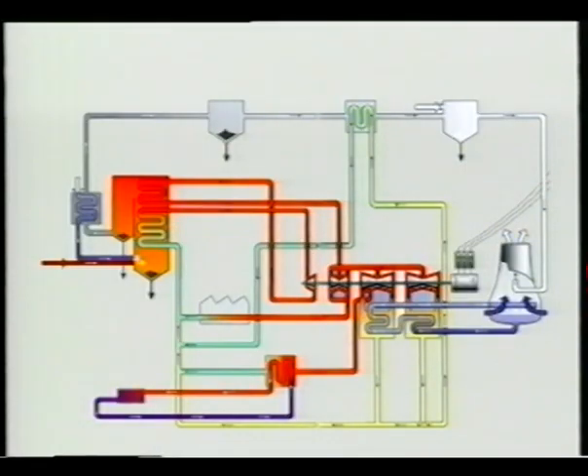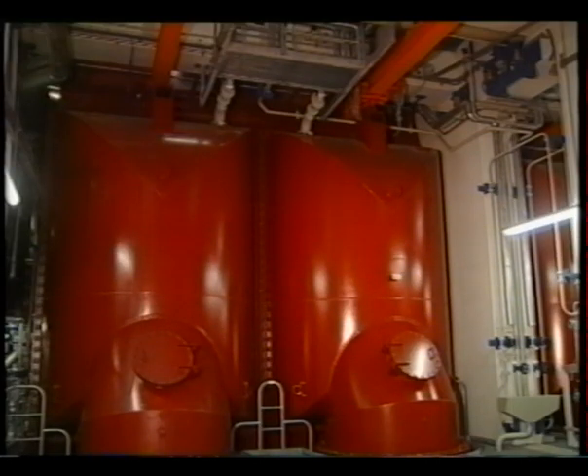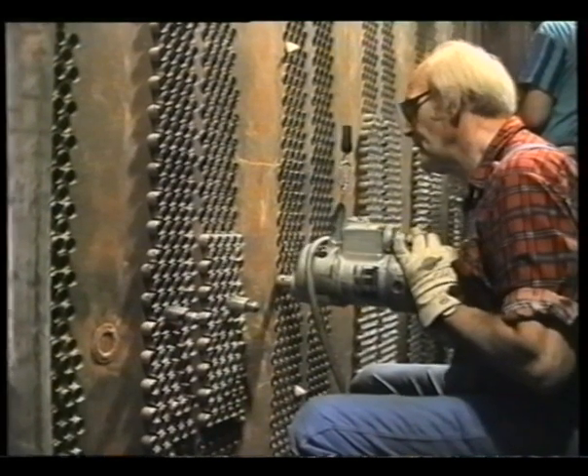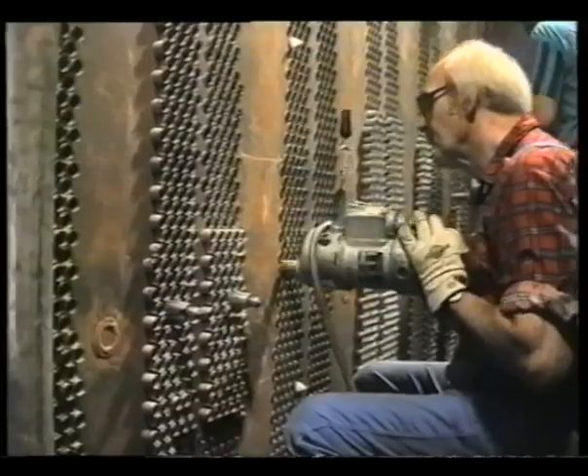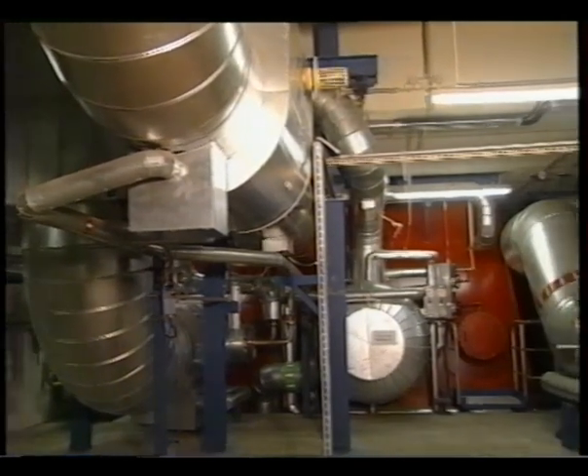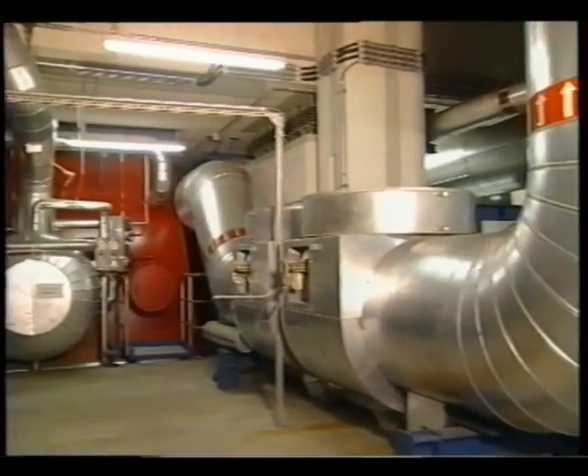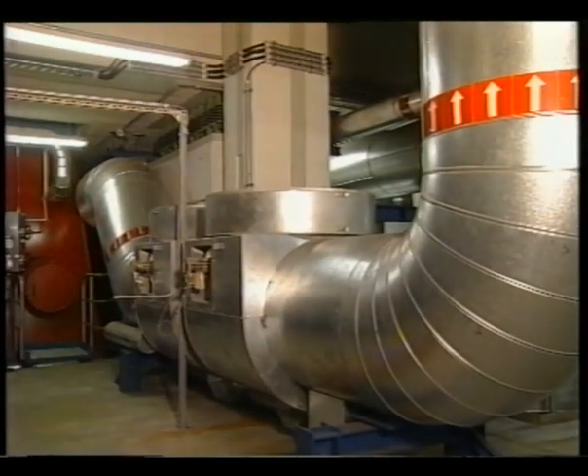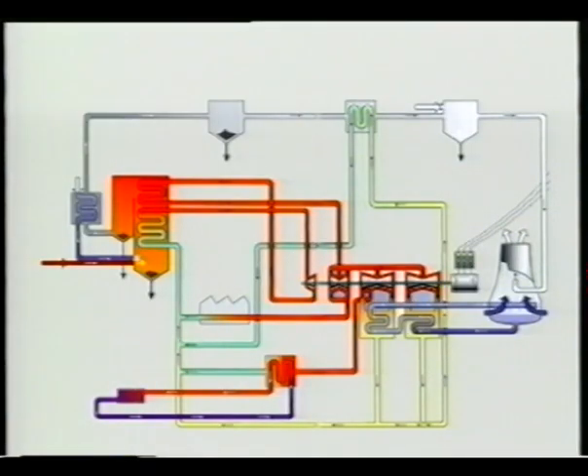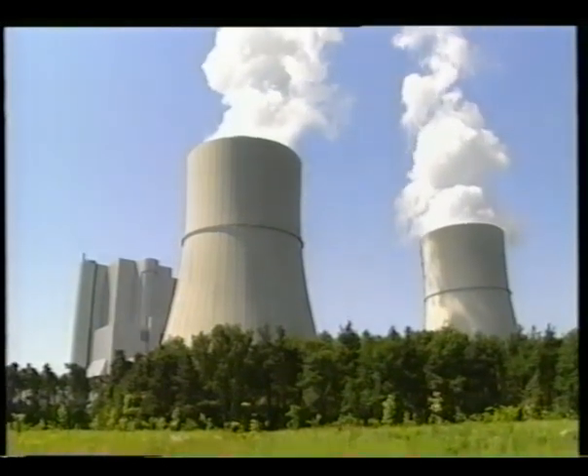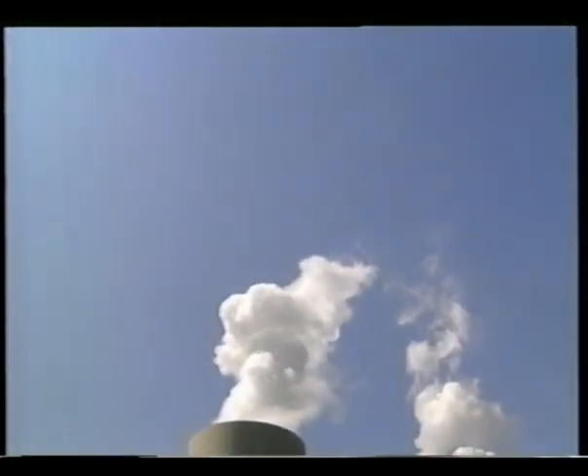After leaving the low pressure stage, the steam is completely used up. The temperature is merely 30 degrees Celsius. In order to turn the steam into water or condensate, the heat has to be extracted. This is done in the condensers with the help of a separate cooling cycle. This is how the condensation heat is transported to the cooling tower. The drift eliminator prevents the water drops from being released.